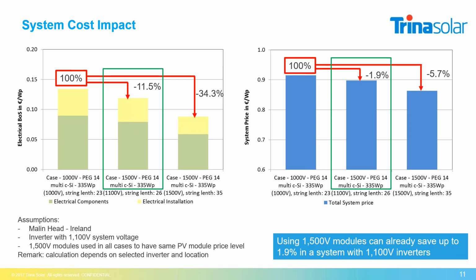The string length increases to 35 compared with 23 in the beginning. That means on the electrical BOS components, the savings in this case are 34.3%, so approximately one third, which comes from the increased voltage from 1000 to 1500 volts, and also means one third fewer connections. This leads to an overall system saving of 5.7%. That means already for a system where you have inverters with 1100 volts, you can save on the system level with 1500 volt modules. For sure, this also depends on the single component prices, but here it's a pure saving due to fewer components and less installation work.